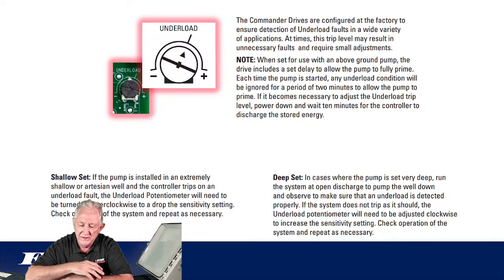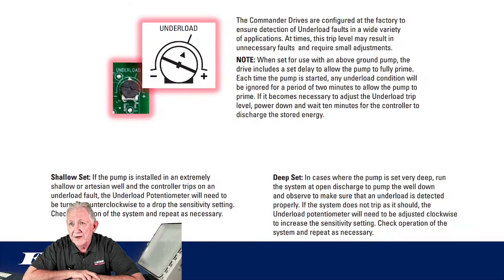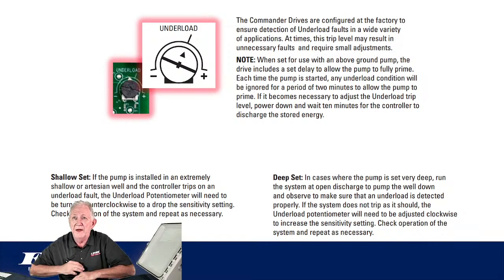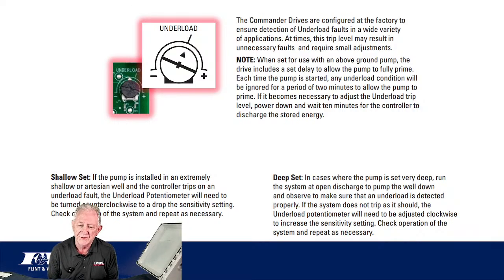I think it's a cleaner explanation. This is the underload sensitivity that's up here. The Commander drives are configured at the factory to ensure detection of underload faults in a wide variety of applications. At times, this trip level may result in unnecessary faults and require small adjustments. So if you're getting nuisance trips, we can cure that by backing off that sensitivity. Down here it says shallow set. If the pump is installed in an extremely shallow or an artesian well, and the controller trips on an underload fault, the underload potentiometer will need to be turned counterclockwise to drop that sensitivity setting, and then check operation of the system and repeat as necessary.